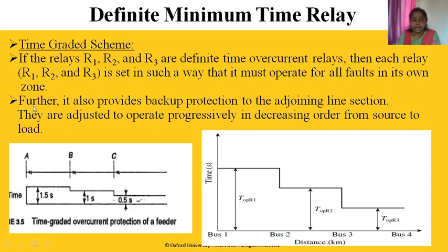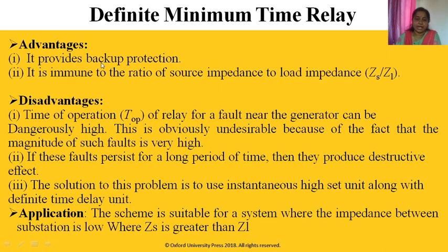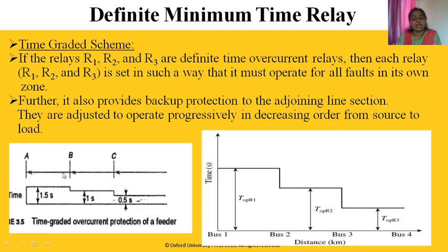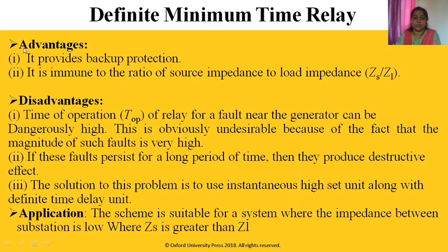Okay, advantages: as intentional time delay is there, it provides backup protection. It is immune to the ratio of source impedance to the load impedance. But what is the drawback? As you can see here, source end has maximum time. So what is our requirement? If fault is near to the source, we need to clear fault in the minimum time, but here that is not possible. This is the drawback of this scheme, that is time graded scheme.